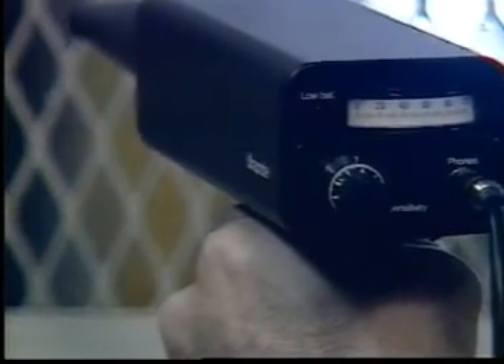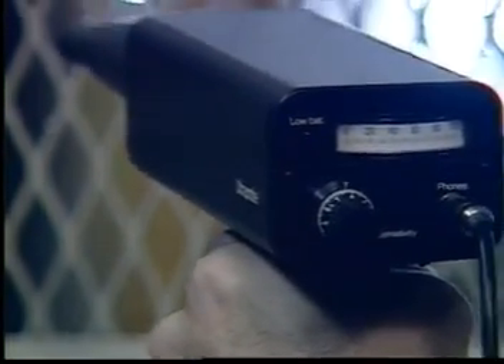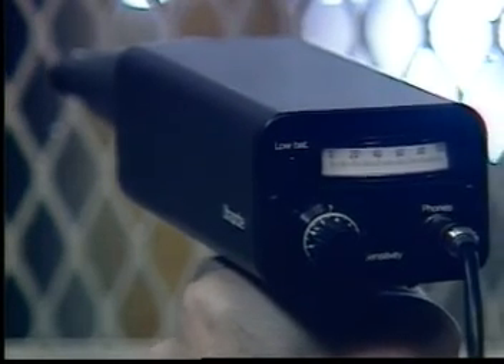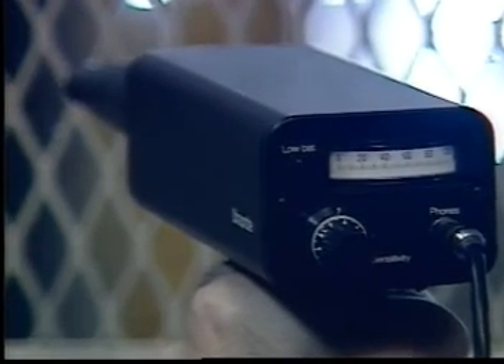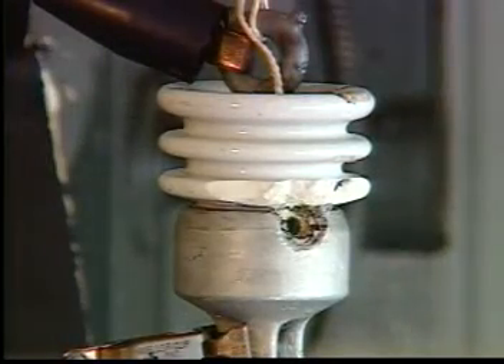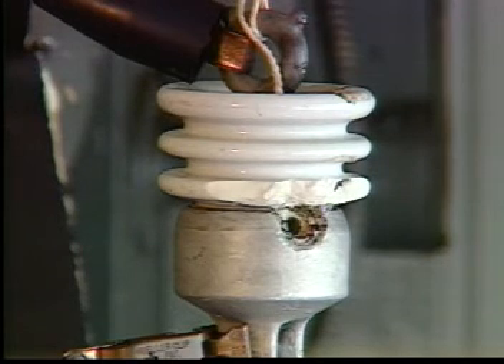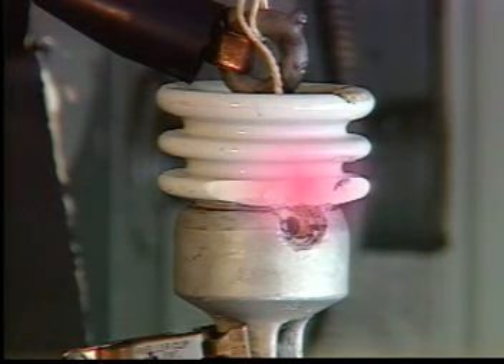Listen to this sizzling sound. This is the sound of tracking over the surface of a cracked insulator. Whereas corona is found at points where electrons jump off into the air, with tracking you'll be able to follow the sound of the electrons running along a damaged site.